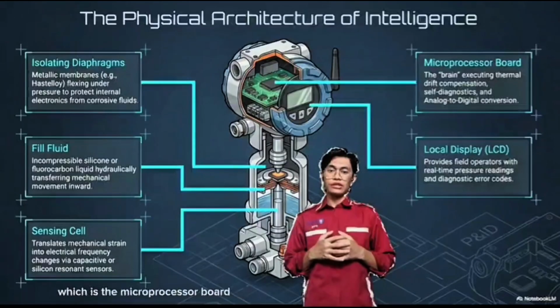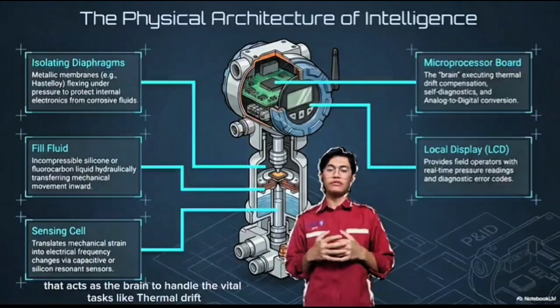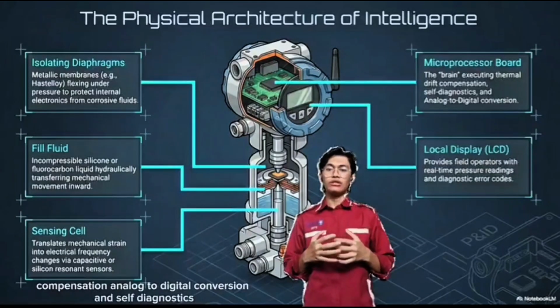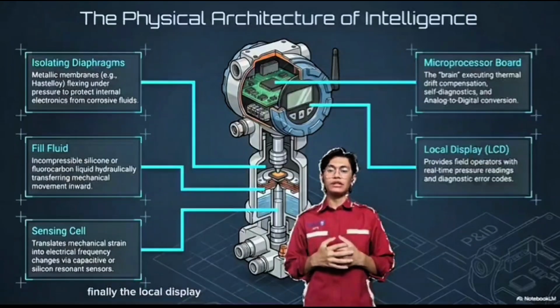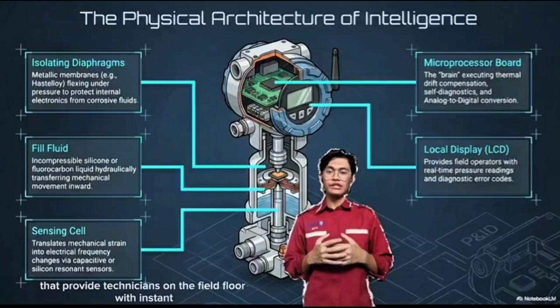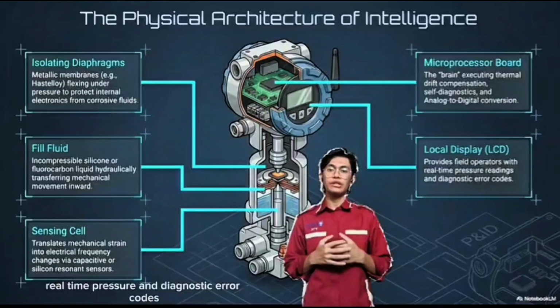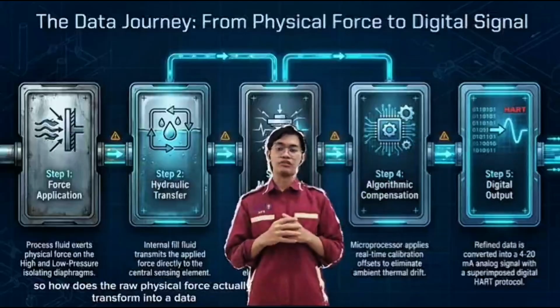Up in the housing sits the microprocessor board that acts as the brain to handle vital tasks like thermal compensation, analog to digital conversion, and self-diagnostics. Finally, the local display, which is an LCD, provides technicians on the field floor with instant real-time pressure and diagnostic error codes. So, how does the raw physical force actually transform into data?